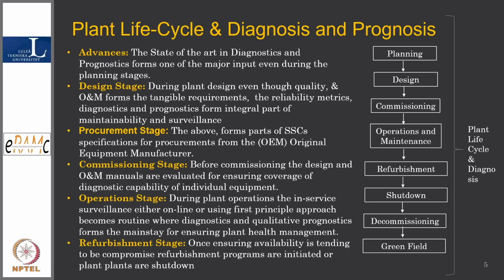The advances in diagnostics, you can see them all through, during the planning stage, when we even start building the system, we are concerned about whether components fail more or less, and which is their weakness. Only then do we go for the design stage, because once we decide our pump, motor, heat exchanger, turbine should be of this size, and for maintaining them we require a manhole to inspect the tubes and all that. So provision for diagnostics is visualized right in the planning stage itself, and then finally the design stage comes into picture.